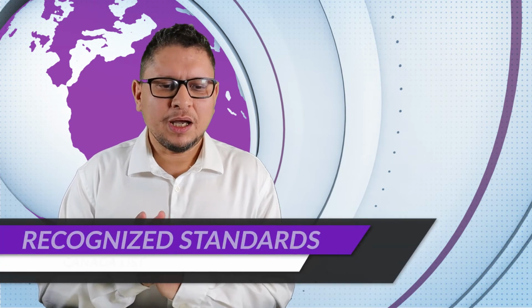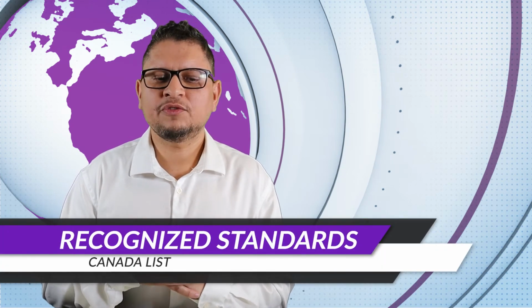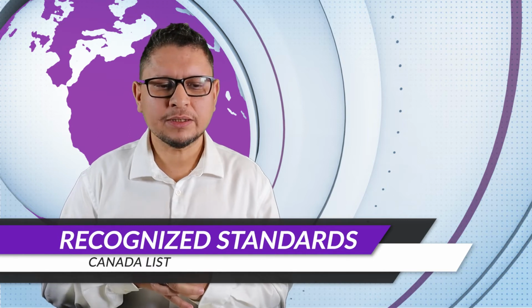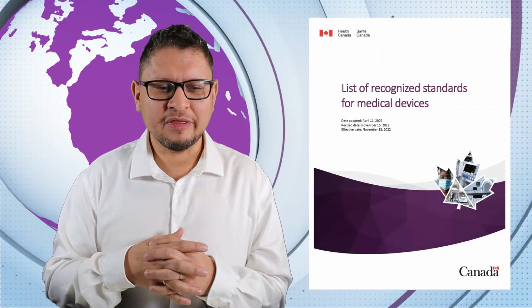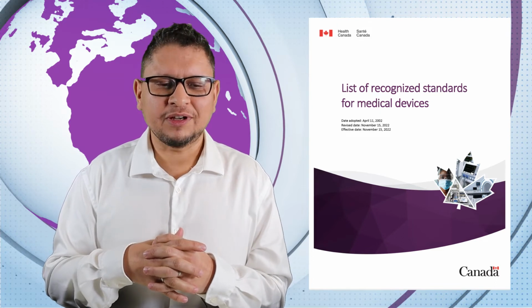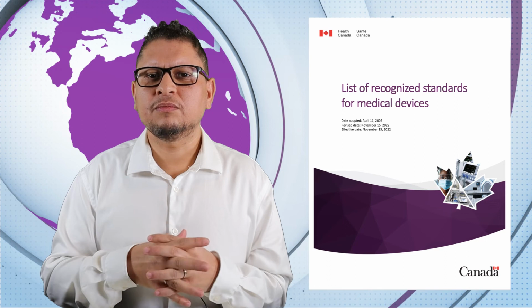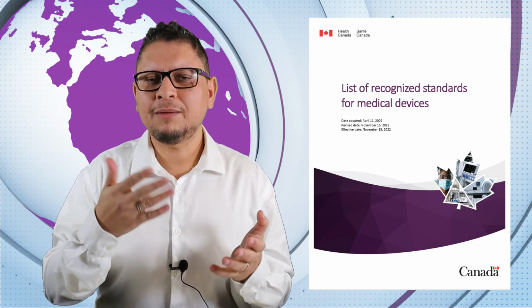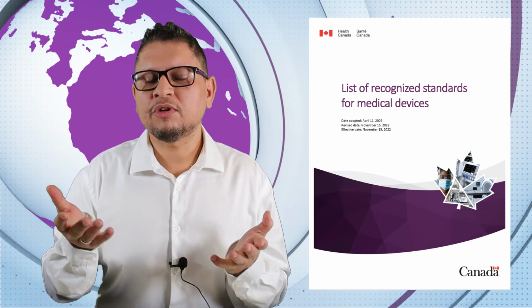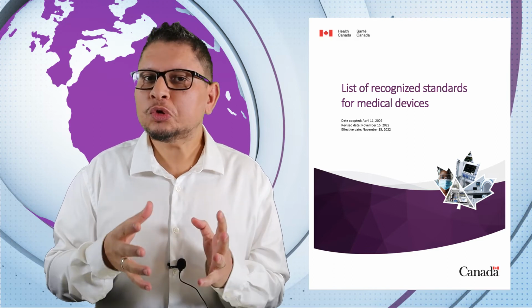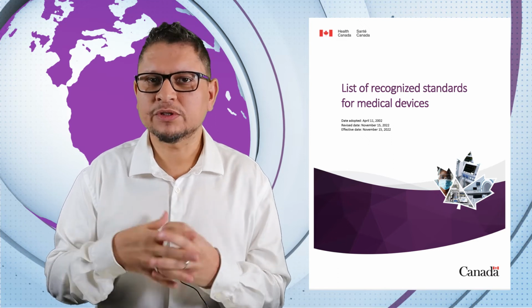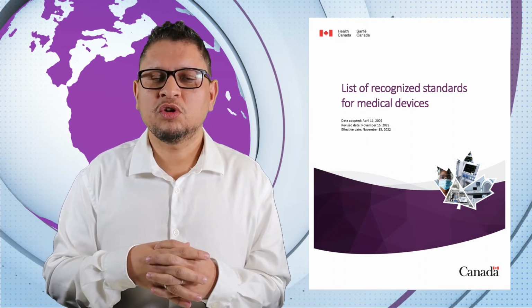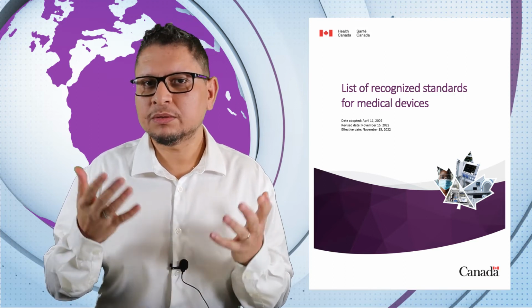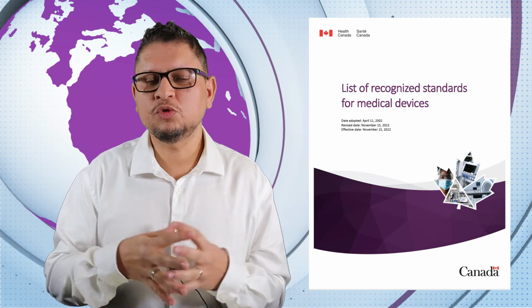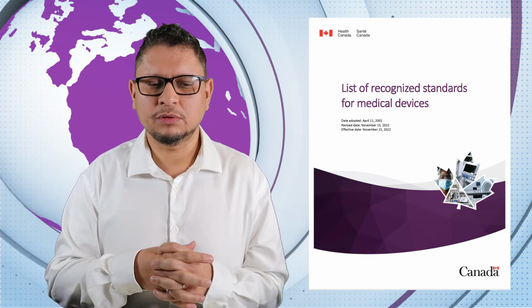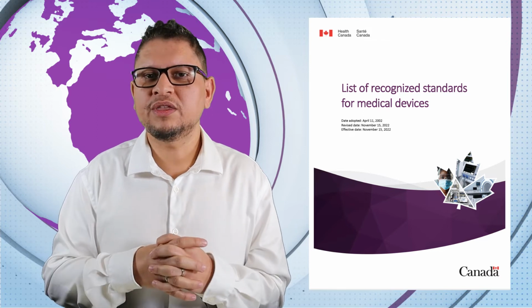Okay, Canada is updating their list of recognized standards for medical devices. So you have mainly all the standards. Just one that I was looking for was not there, which is the ISO 13485 2016. I know that Canada is now using MDSAP for their quality review, but ISO 13485 is also part of MDSAP. So I'm not sure if this is a miss or if this was made on purpose, that ISO 13485 is not recognized as a harmonized standard for Canada. But mainly, as I've said, it's used for MDSAP, so it's embedded inside MDSAP. So not sure why it's not listed, but this is the only thing that I was looking at.